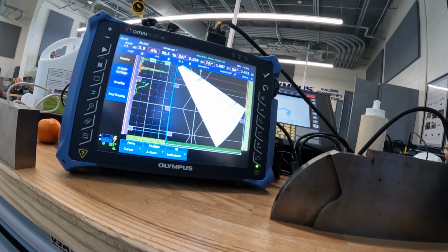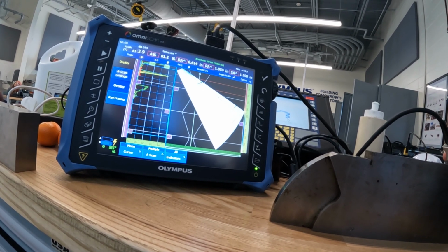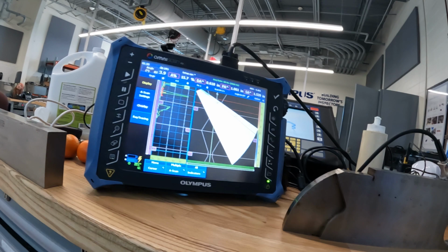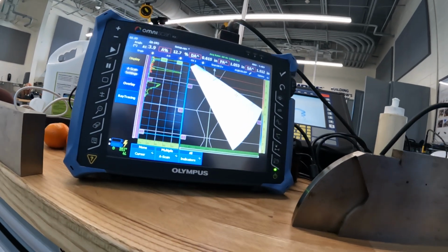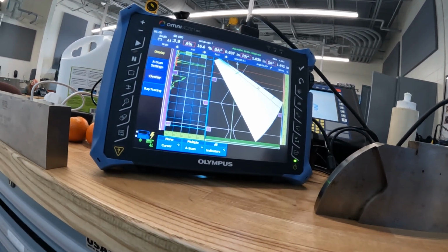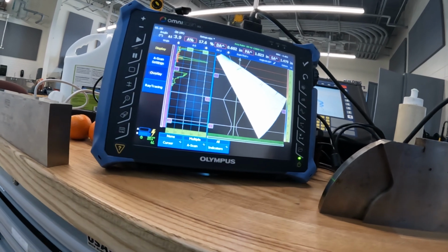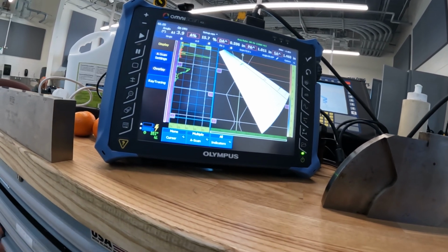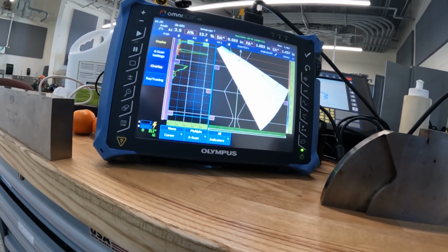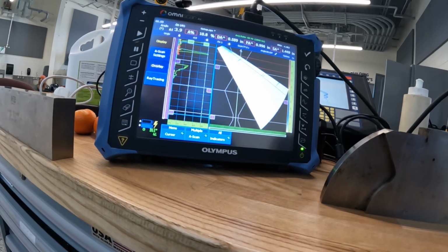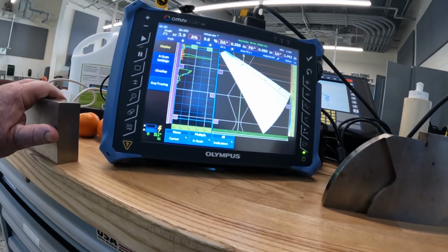I'm getting 77, 78, 79, 81. Okay, I got it. So typically the tolerance is around 5% on this. So this means that your sensitivity is a relatively good calibration. So once we've got that, then the next thing is the TGC.